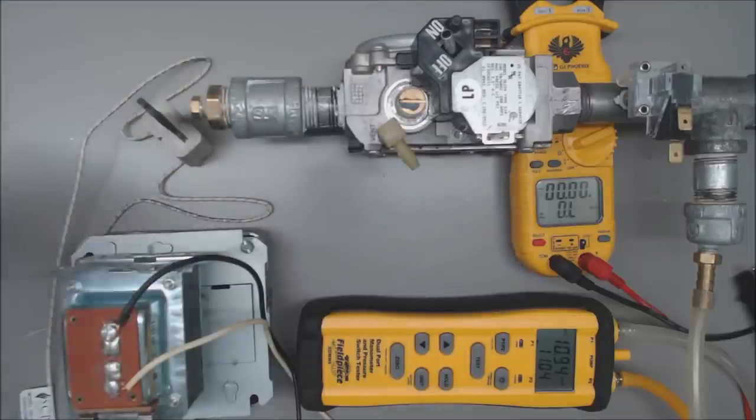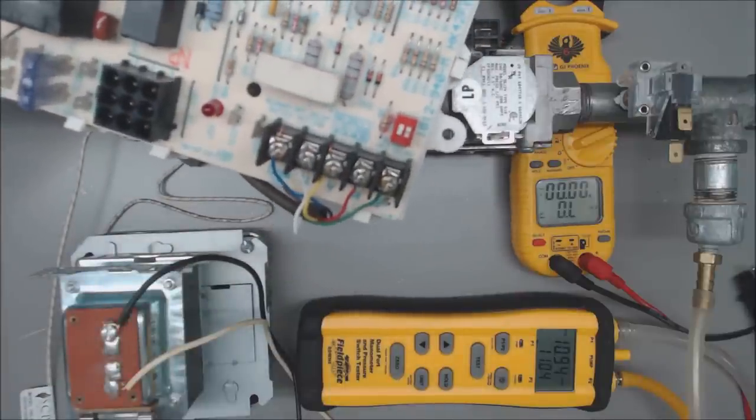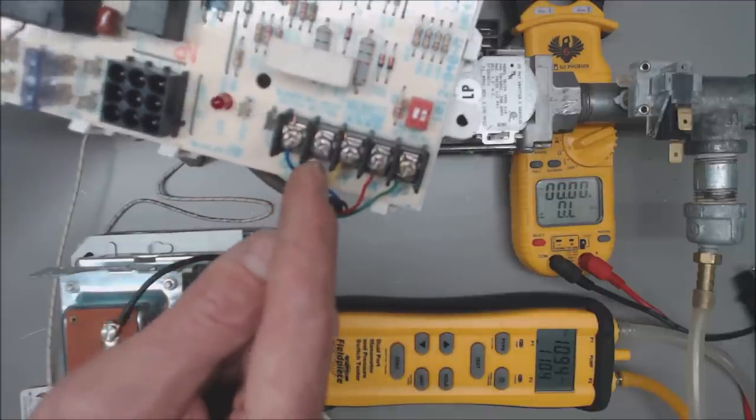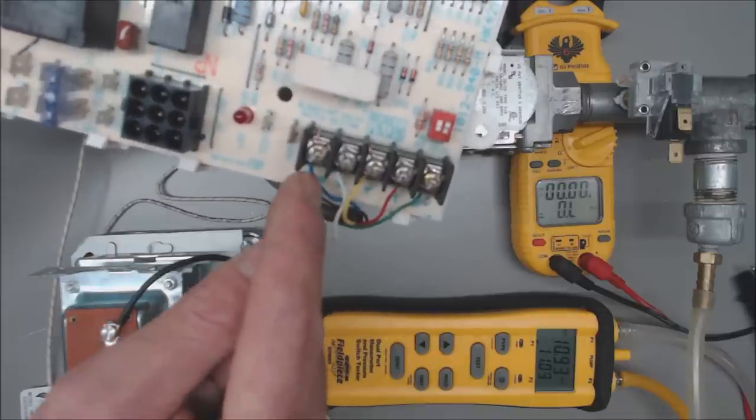In order for this to turn on you have to go through the sequence of operations. First, you need a call for heat at the thermostat which means that R and W are touching. Then at the control board, the board sees 24 volts on W and you can read it with your multimeter from W to common.